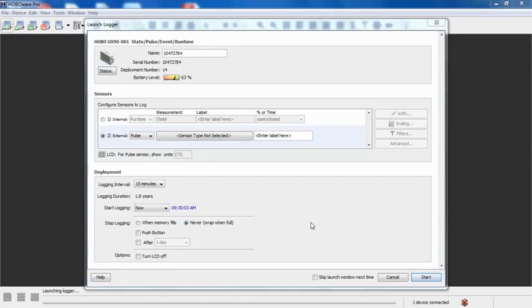When we have customers who are logging data from a WattNode or a Veris device, we usually suggest logging once a minute or slower. Obviously, if you have a circuit with a device that you want to log that has a very fast duty cycle, less than a minute, then we need to throttle that back so we can capture that. But basically, the more pulses we can get per interval, the more relevant our data is going to look to us.